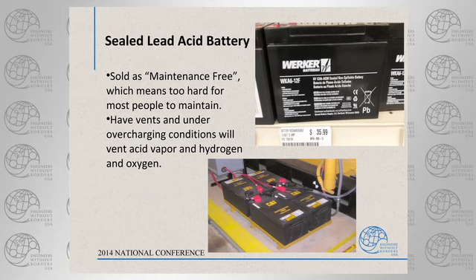So this, however, is more commonly what you will see as a sealed lead acid battery in a developing world context. These are sold as maintenance-free, which means you can't do maintenance on them, even if you'd like to. And what this means is that it's a sealed vessel, and under a severe overcharge, it will actually vent hydrogen as it overcharges. So this can present some serious problems because you are losing electrolyte levels, and there's no way for you to open this up and recharge those electrolyte levels.